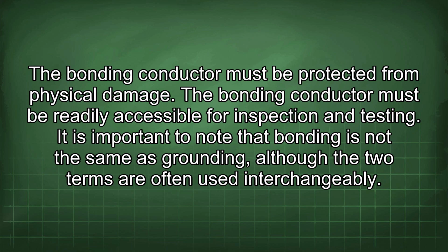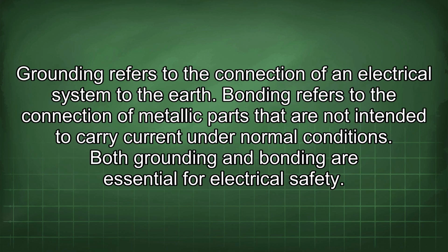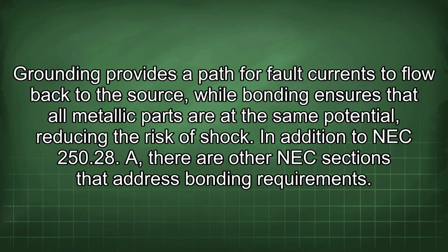It is important to note that bonding is not the same as grounding, although the two terms are often used interchangeably. Grounding refers to the connection of an electrical system to the earth. Bonding refers to the connection of metallic parts that are not intended to carry current under normal conditions. Both grounding and bonding are essential for electrical safety. Grounding provides a path for fault currents to flow back to the source, while bonding ensures that all metallic parts are at the same potential, reducing the risk of shock.